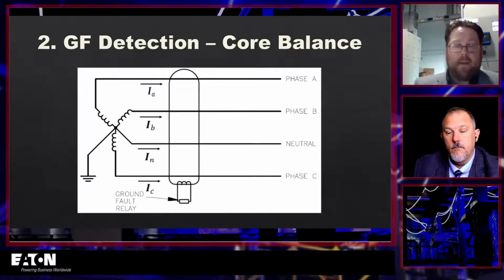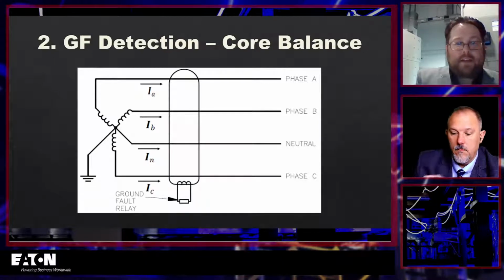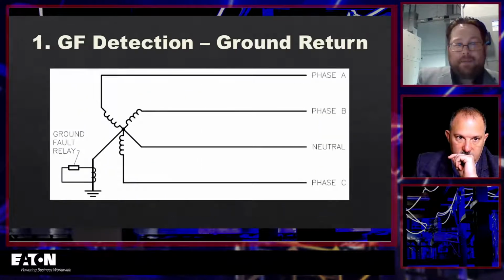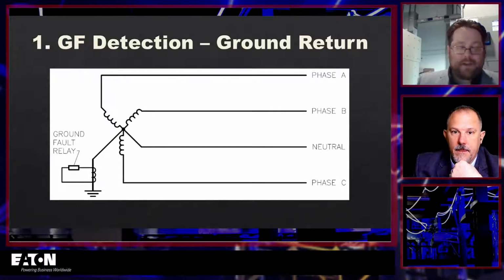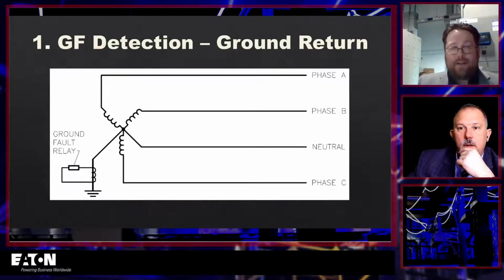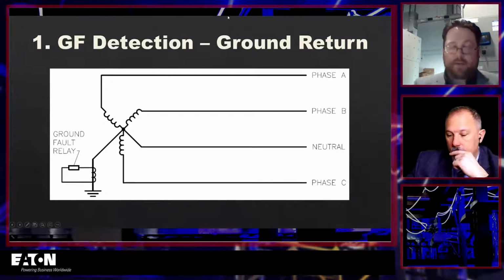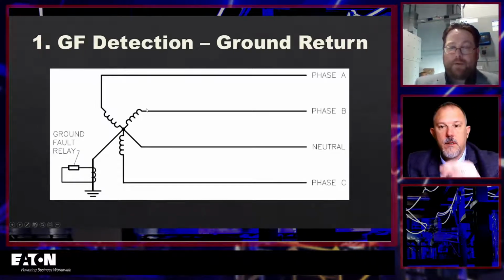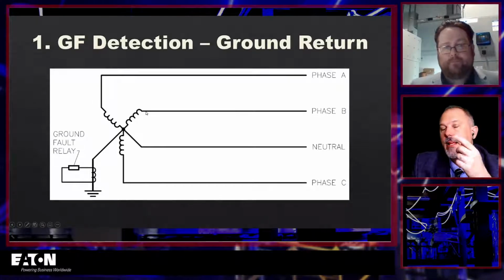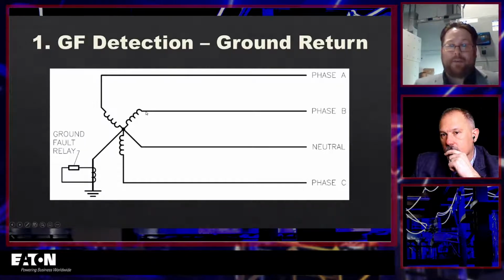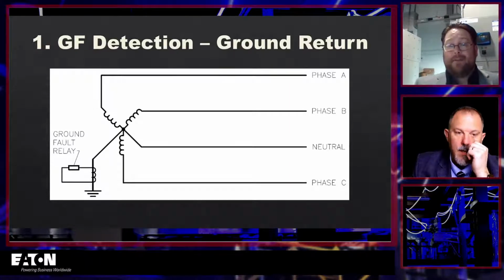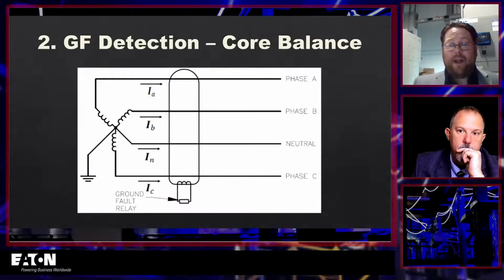Yep, absolutely. I forget what the title was on the last slide. The ground return or ground fault detection; another name would be source ground. Another term in the manual is source ground. Okay, perfect. It measures ground directly. So we're actually measuring the ground current directly. Versus zero sequence, on your second slide, where we're not actually measuring current in the ground path. We're doing that summation, a calculation of what it is. We're not actually measuring it.